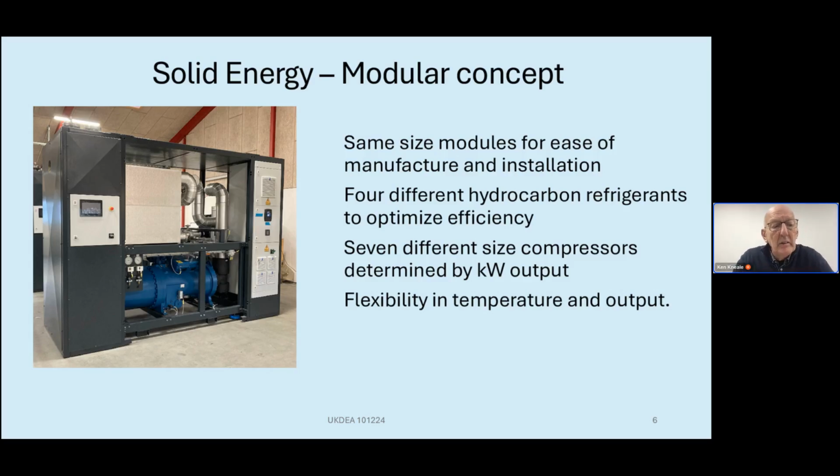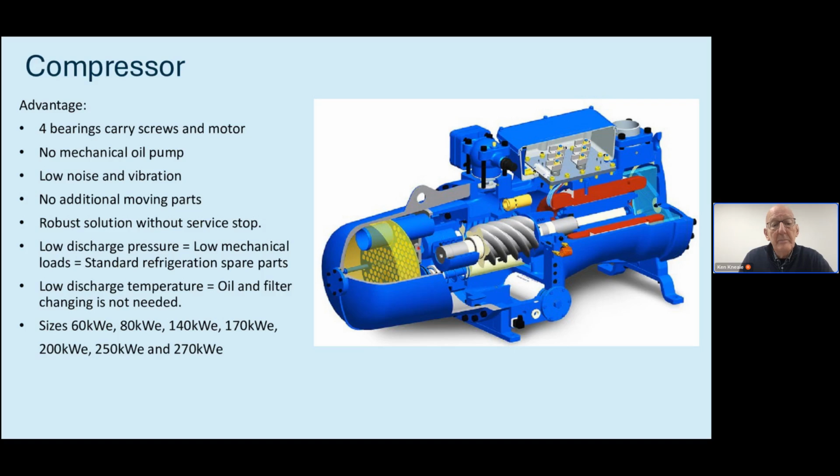I actually can't tell you the details of that unit. That unit on the photograph, it could be an 800 kilowatt heat pump that's developing 65 degrees, or it could be an 800 kilowatt unit that's developing 150 degrees. The only reason I can tell it's approximately 800 kilowatts is because I can see that it's quite a large compressor. The compressors are the heart of our heat pumps.